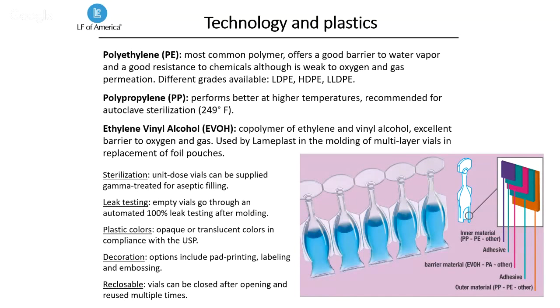We saw that polyethylene is weak in terms of barrier with oxygen. So if you have a product that needs an oxygen barrier because it's sensitive to oxidation, then we have the capability of molding the EVOH in multi-layer vials. As you can see in the image on the right at the bottom, we can customize the layers of plastic. So the inner layer, which is in contact with the product, can be either a polyethylene or a polypropylene or a different type of material, starting from the specific requirements of the solution.